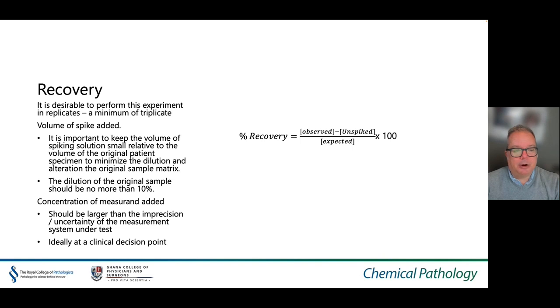In terms of general performance, the dilution of the original sample should be no more than 10%. The concentration of the measurand added should be larger than the imprecision or measurement uncertainty of the system under test, and ideally at a clinical decision point. Percentage recovery can be calculated by the formula indicated.